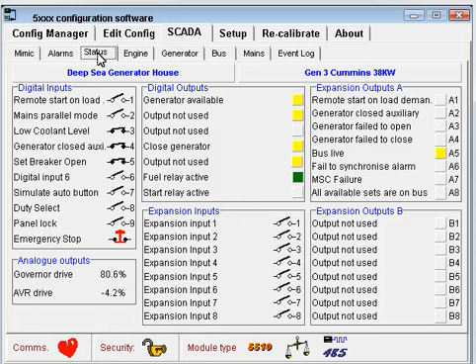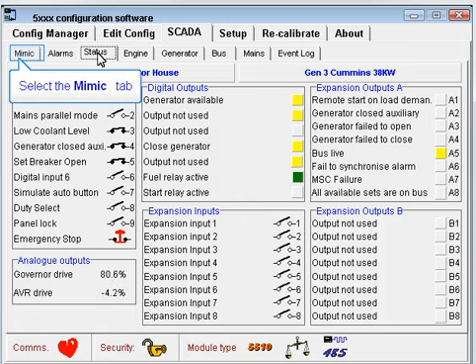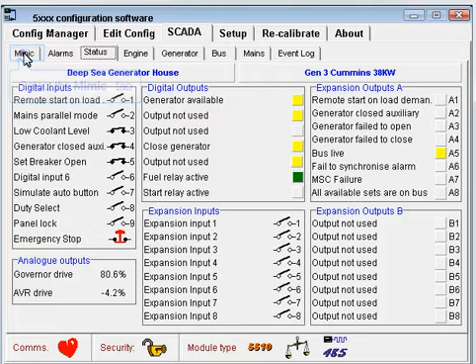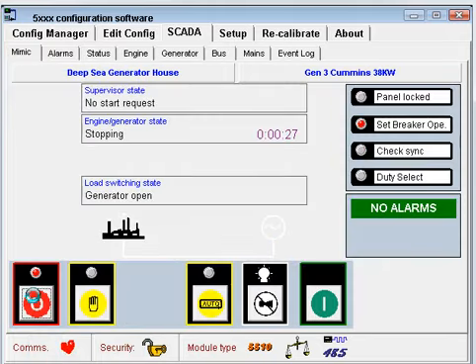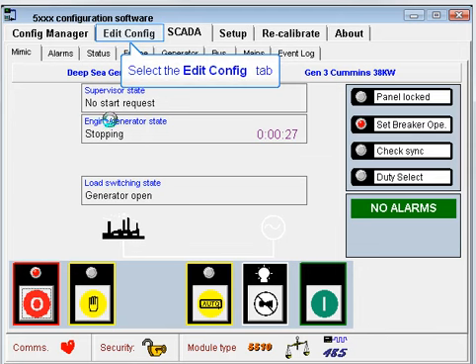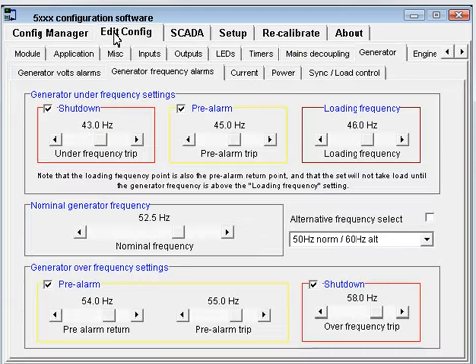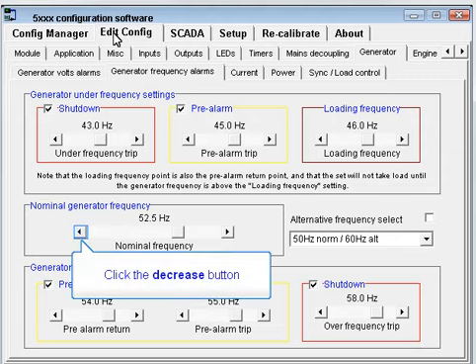Go back to the mimic page to stop the engine. Now we've tested that the frequency can be increased, we need to check we can decrease it successfully also. Lower the frequency 2.5 Hz below the nominal frequency. We're checking the range of movement we have over the engine speed.